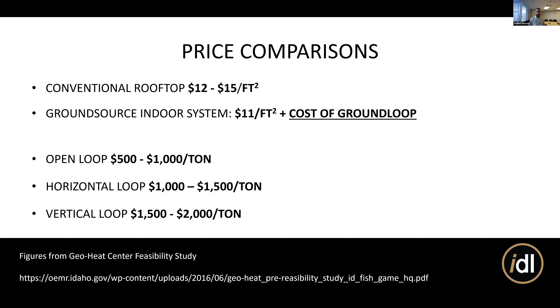So that's why I'm trying to get to the heart of the design today, which is a hybrid system. So instead of just looking at, we've got really cold winters, let's size it to make sure we get the most out of it all winter long, you're going to be drilling a lot of extra boreholes. Instead, look at sizing the system on your smaller load, which in this situation would be your summer cooling. And during the wintertime, no, your ground source isn't going to be able to make up for that. It might fall short on a few of the coldest days.